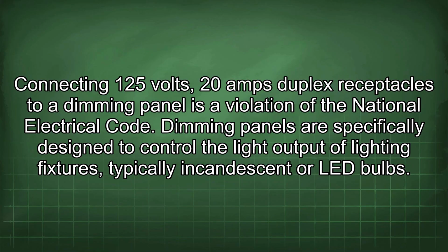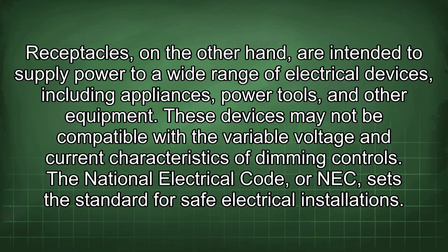Connecting 125 volts, 20 amps duplex receptacles to a dimming panel is a violation of the National Electrical Code. Dimming panels are specifically designed to control the light output of lighting fixtures, typically incandescent or LED bulbs. Receptacles, on the other hand, are intended to supply power to a wide range of electrical devices, including appliances, power tools, and other equipment. These devices may not be compatible with the variable voltage and current characteristics of dimming controls.